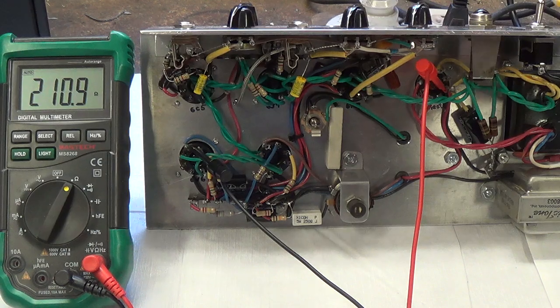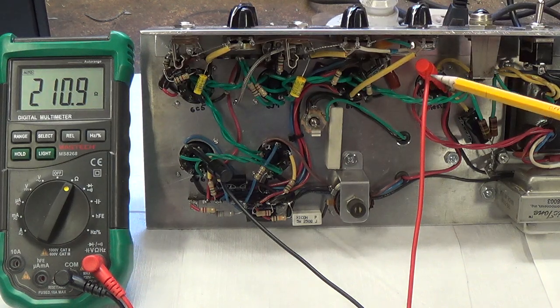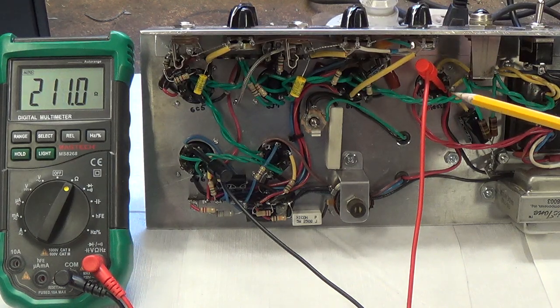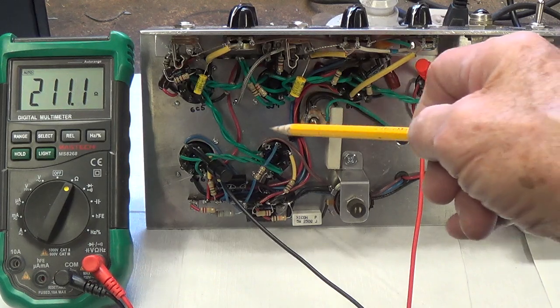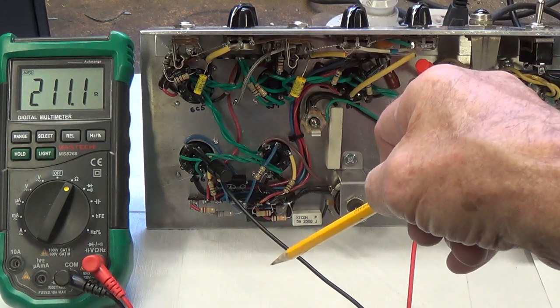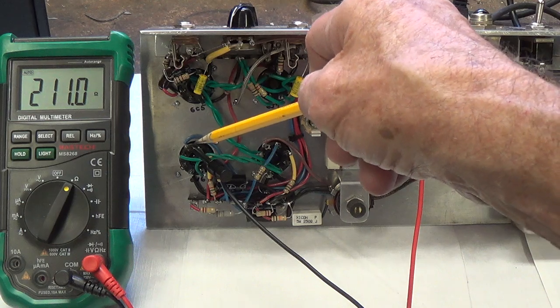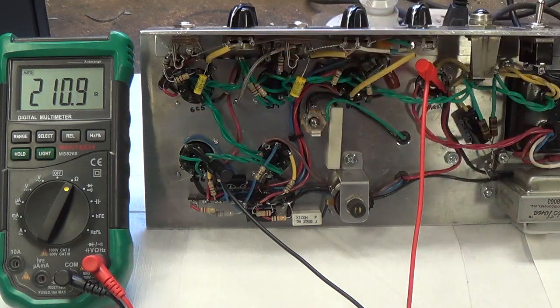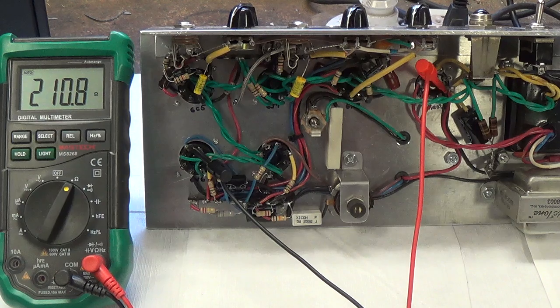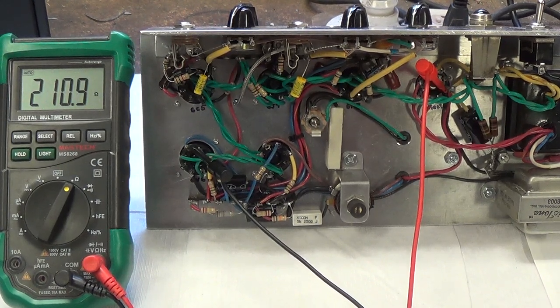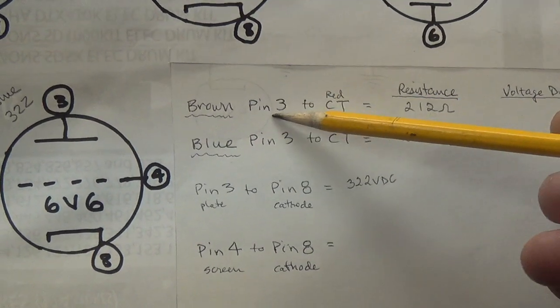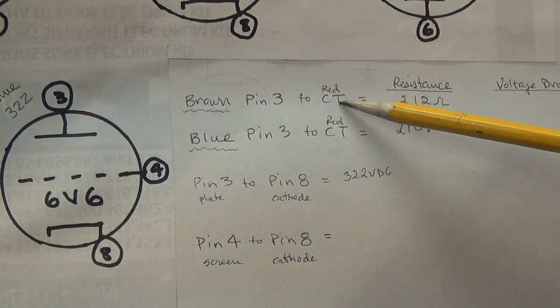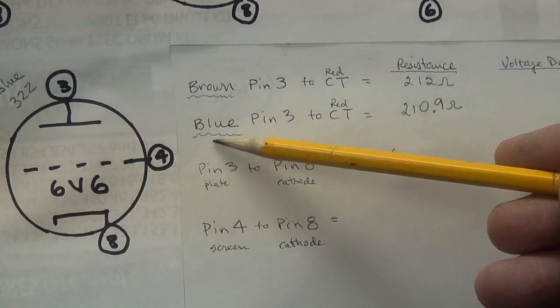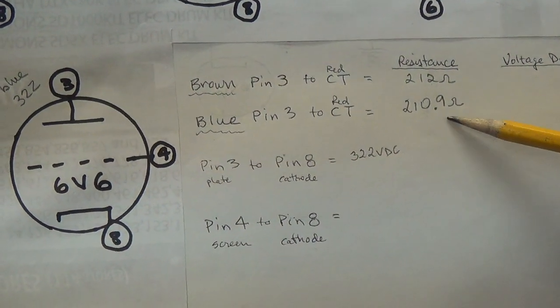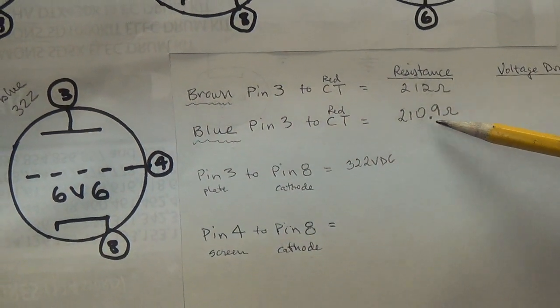Now with the amp off, the center tap lead is still connected where it was for the brown plate measurement. I move the other lead over to the blue plate pin, and it measures about 210.9. I always write them down: brown to center tap, 212; blue to center tap, 210.9. Are they different? Yes, but not by much.